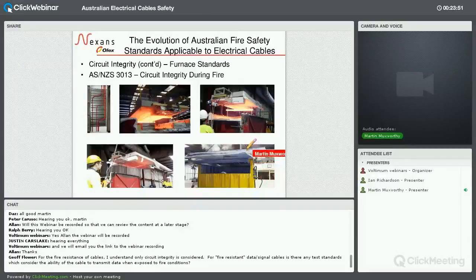Just some pictures of the fire test itself. The photo on the far left shows how the cables are mounted on a cable tray prior to doing the test. And hopefully you can see and get a feeling for the severity of this particular test. This is a photo of the furnace lid being removed so that it can be taken over to do the water spray test. As you can see, the cable tray and the cables are glowing red hot, and that gives you some indication of the amount of heat that's in there.